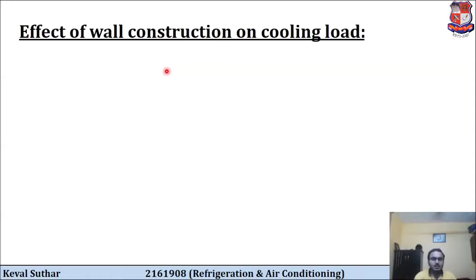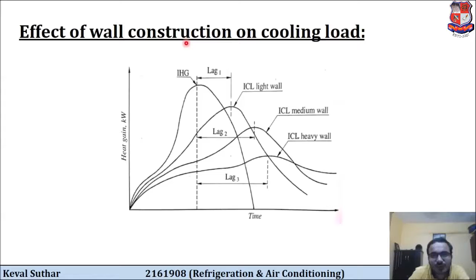Now the effect of wall construction on cooling load. Here is a similar kind of graph of instantaneous heat gain and instantaneous cooling load. The only difference is that here we are taking 3 cases of light wall, medium wall and heavy wall. You can see that the time lag in the light wall is minimum, in medium wall the time lag is slightly more, and the time lag is maximum in case of heavy wall. So this is the effect of the type of wall which we are using in our building on the cooling load.